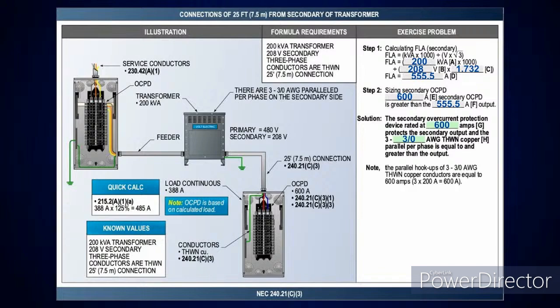Well, a 3-aught's good for 200 amps. So three 200 amp parallel conductors is going to give you 600 amps. And if you notice, did I change the calculation? No. The calculations have to still be the same. Be careful, because if you all of a sudden at the end of your statement put in an adjustable circuit breaker, then you're going to have to change your equipment ground.